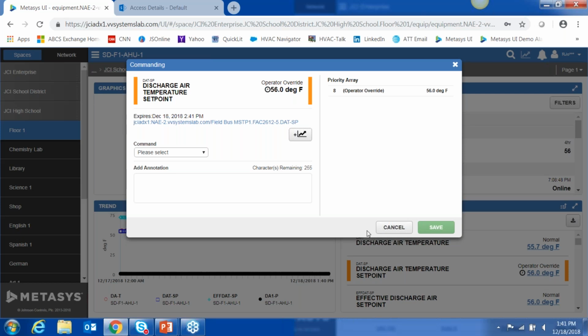So I went back into the commanding dialog, and under this priority array, this is what's new at release 10. It now shows you exactly what priority was given to the command I gave. It's an operator override, and this is a BACnet standard. BACnet standardized how multiple different commands could be handled using different priorities, with a 16-array priority command structure that BACnet defines. By exposing this, our operators now have that much more information at their fingertips to know why a command is operating the way it is.